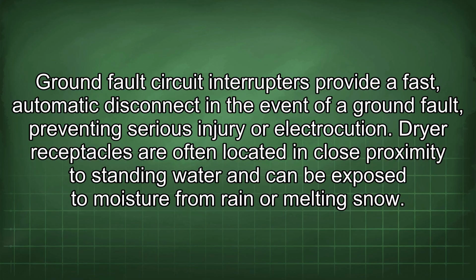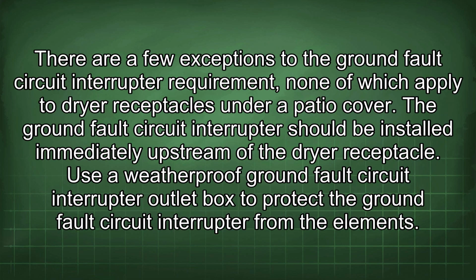electrocution. Dryer receptacles are often located in close proximity to standing water and can be exposed to moisture from rain or melting snow. There are a few exceptions to the ground fault circuit interrupter requirement, none of which apply to dryer receptacles under a patio cover. The ground fault circuit interrupter should be installed immediately upstream of the dryer receptacle. Use a weatherproof ground fault circuit interrupter outlet box to protect the ground fault circuit interrupter from the elements.